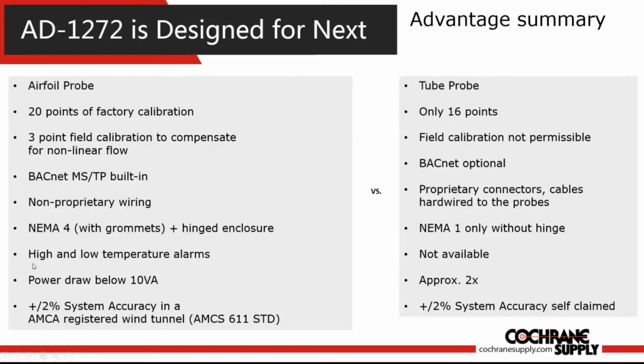Another big advantage is actually the high and low temperature alarms for AD-1272. The competition has high and low alarms for velocity, but not for temperature. Again, the power draw is also better than the competition by a factor of 2. And the system accuracy, so the number of sensors that we make as standard based on the size of the duct, whether it's 30 by 60 or 10 by 30, different combinations of probes and sensors that go in. We are tested in an AMCA registered wind tunnel to meet a specific standard. And our competition is self-certified. So those are the main advantages from a specification standpoint.